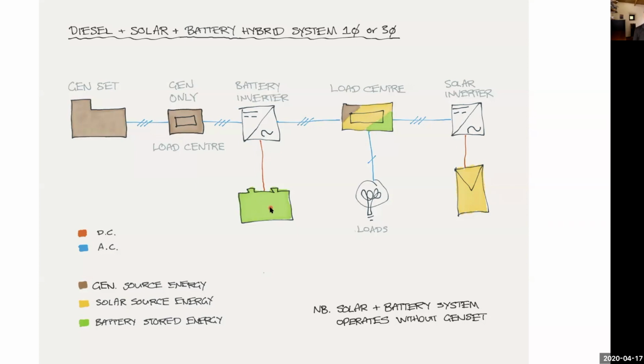The advantage of this is these AC solar inverters generally are very cost effective, certainly as you scale up in size, and they operate at relatively high string voltages. So it's possible to use conventional stringing arrangements. Running a single phase inverter at 400 or 500 volts DC makes for very easy arrangement of panels, and in three phase even higher.